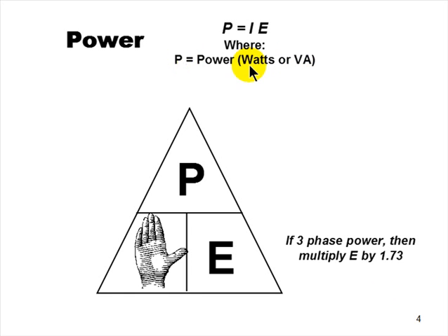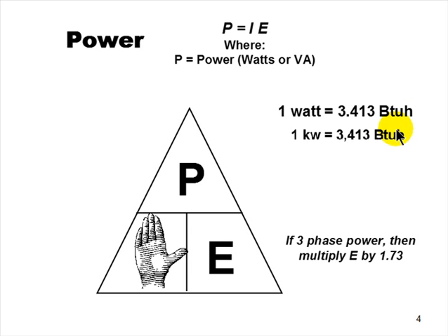How do you get the VA of a transformer? Well, you multiply the volts times the amps times 1.2. That's your VA that you need, volt amps. 1 watt, remember, is equal to 3.413 BTUs, and 1 kilowatt, K is kilo, thousands, not thousandths. Thousandths would be milli. Kilo is times 1,000. All right, so 1 kilowatt, 1,000 watts, is equal to, move it 1, 2, 3 decimal places, 3,413 BTUs. Why am I telling you this? They're going to ask you that in the test.